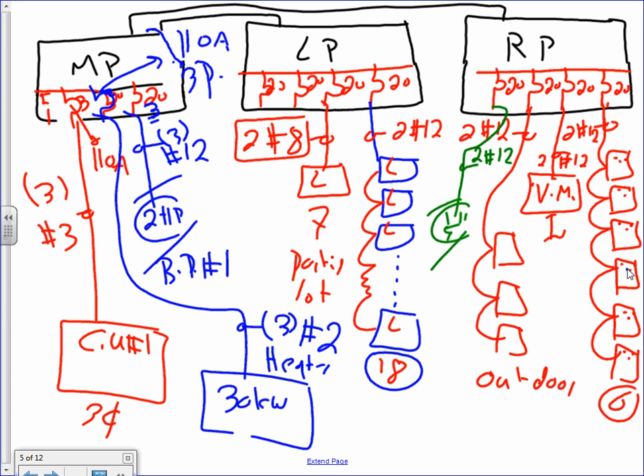And then I have a 2 horsepower boiler pump, and I fit this one from a 20 amp circuit, 3-phase. From a 20 amp circuit 3-phase. How the heck did I come up with these sizes here for the branch circuit? You're going to see in the next slide. Okay? So for these receptacle panel and lighting panel, there's a calculation coming, guys, to verify these numbers. Why did I come up with what I came up with? Can I have thumbs up, Chad? We understand? The reason why I threw these at you is because that's the most important thing for us.